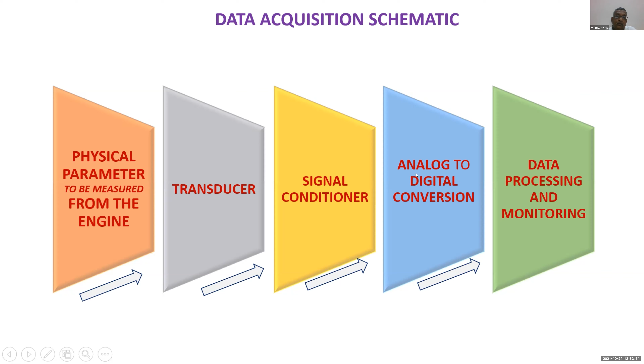Pressures again, for the fuel and oil, this is air medium and this is fuel and oil. We use strain gauge pressure transducers conditioned by National Instruments PXI conditioners, again at 200 samples per second. Let me not go through the whole thing. I'll come over here where there are high speed, high frequency requirements. If you take vibrations, we sample at 20 kilo samples per second.